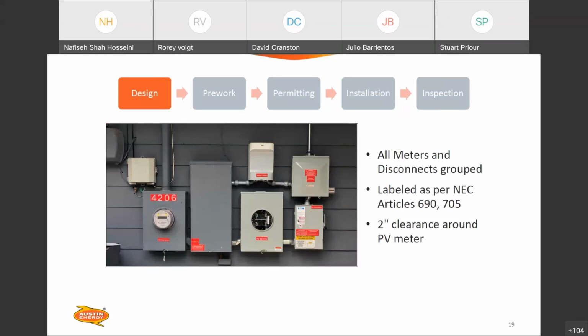So here's a good example of an equipment wall that's installed according to national code and our local ordinances. Notice that meters and disconnects are all grouped within 10 feet of each other. There's no need to go to another location on site to do any sort of service work on the system. It's all right there in one spot. So that's ideal. If you, for some reason, do need to install that meter can at a different spot on the premises, that's when the meter variance approval comes into place, which should be handled during the design process too, because you want to have that variance approved before you install the meter can.